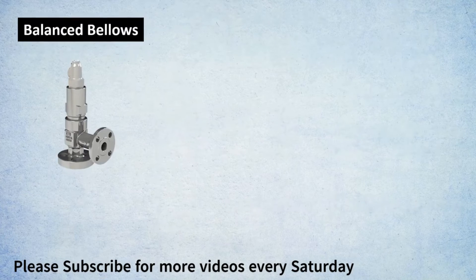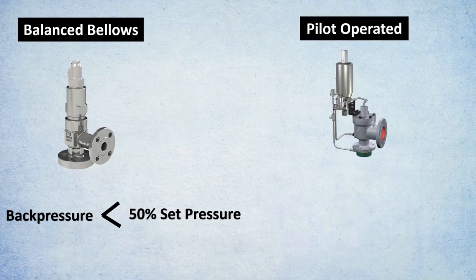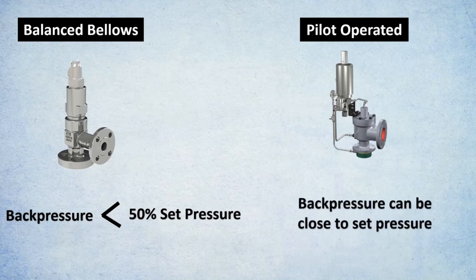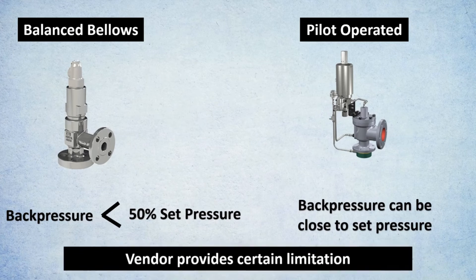For a balanced bellows relief valve, the back pressure should be less than 50 percent of the set pressure. For pilot operated relief valves, the back pressure can be close to the set pressure — theoretically up to 100 percent, though vendors will provide certain limitations. Whenever the back pressure is greater than 50 percent, you must go with a pilot operated relief valve.